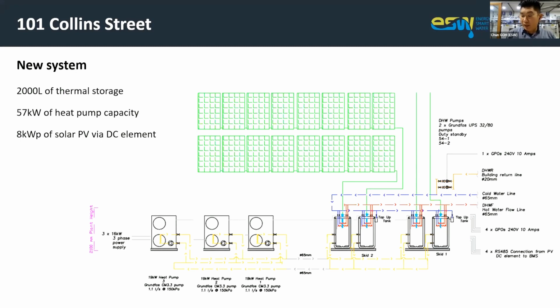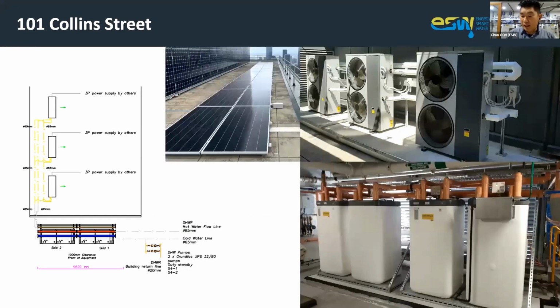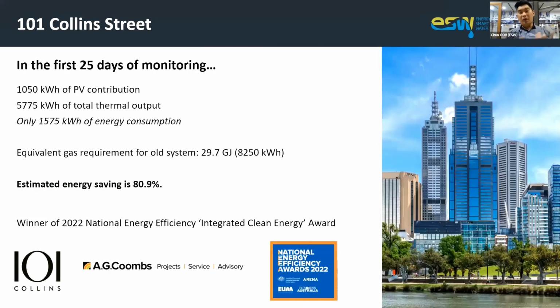Stage 2 will be upcoming, where it's going to supply from level 13 to 34, which would be something similar as well. For this system, the heat pump would be operating very minimally, where we heat up the water to 75 to 80 degrees, and then the rest will be topping up to 85 degrees maximum from the solar PV. The solar PV will generate the power to run the heating element as well. So it's a combination of systems.